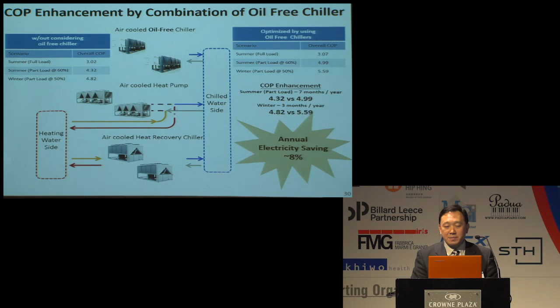And we will also introduce what we call the energy optimization solutions. Now, the best way I can describe this is like an autopilot on the airplane. Basically, what this system does, we build a lot of sensors, much more sensors than we ever built before. So we are monitoring the ambient temperature, humidity, and the cooling load at the same time. With all these figures, the computer, through an algorithm, will determine what's the best setting for the chiller, cooling tower, and the pump. So basically, we optimize the settings so that we provide the cooling load for the building, for the occupants, but with minimum amounts of energy.